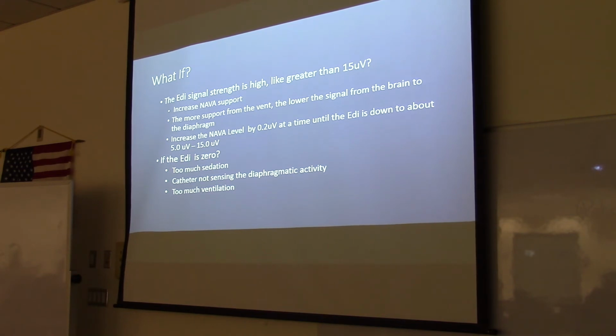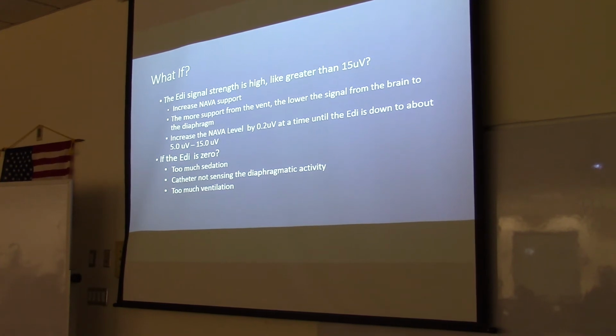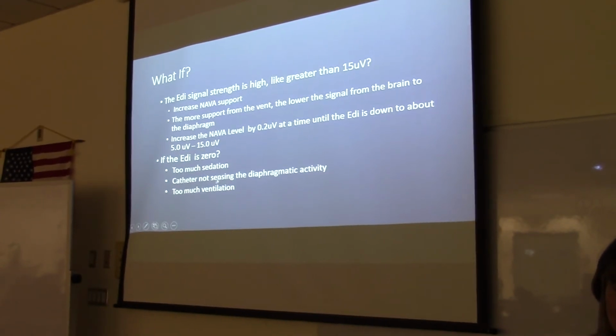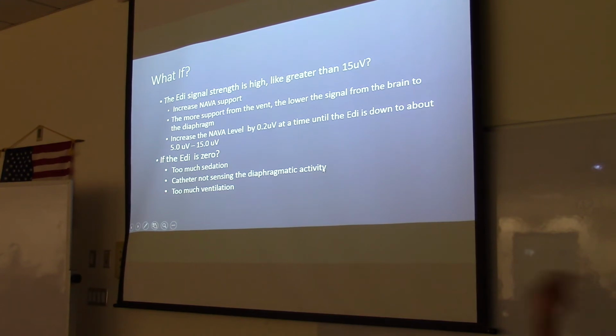But what if the EDI signal is 0? Because that can happen, where you get no signal from the brain at all. And that could be because the patient is heavily sedated, that knocked out the drive to breathe. The catheter is not sensing the diaphragmatic activity. That means that the catheter came out of position. Or it could be that we're just over-ventilating the patient and they have no need for more breaths. All right, so circle that, put a star by that. You'll have to know why you're getting a 0 signal.